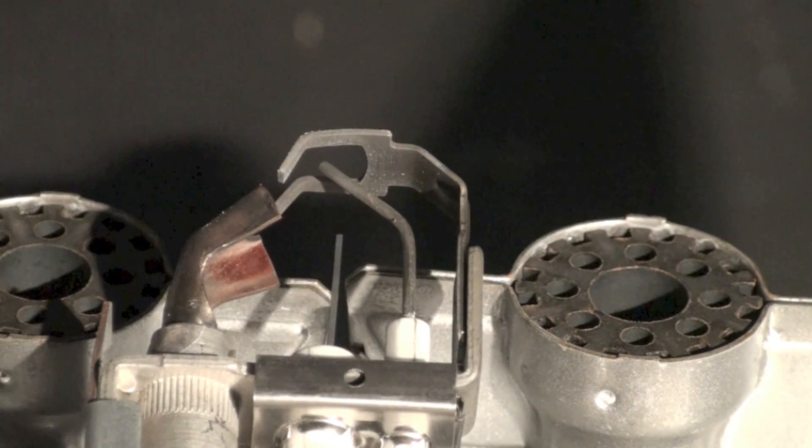Now the flame rod can be cleaned, but you got to be careful there and not break the hot surface igniter. If you're going to break the hot surface igniter, you got to replace the entire pilot assembly. So we'll watch that through another cycle.